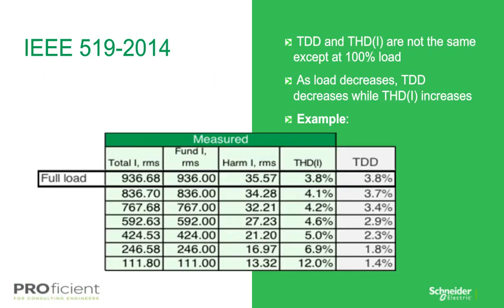So taking a further detailed look into this, and more of a field application approach, the chart that we provided below shows basically the difference between THDI and TDD. The blue highlighted area is what the harmonic analyzer measures, and which we actually reported on a DC load at our plant in Salem, Oregon, as it is a production facility where we manufacture our active harmonic filters. And please note that the amplitude of the harmonic current decreases as the load decreases. However, for THDI, which is the harmonic current divided by the fundamental current at the time of the measurement, as the load decreases, THDI increases.